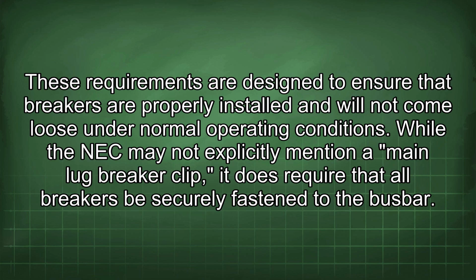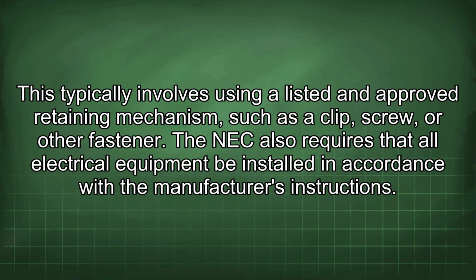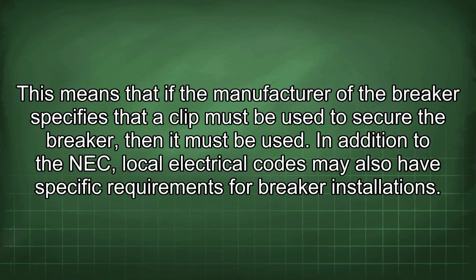While the NEC may not explicitly mention a main lug breaker clip, it does require that all breakers be securely fastened to the busbar. This typically involves using a listed and approved retaining mechanism, such as a clip, screw, or other fastener. The NEC also requires that all electrical equipment be installed in accordance with the manufacturer's instructions. This means that if the manufacturer of the breaker specifies that a clip must be used to secure the breaker, then it must be used.